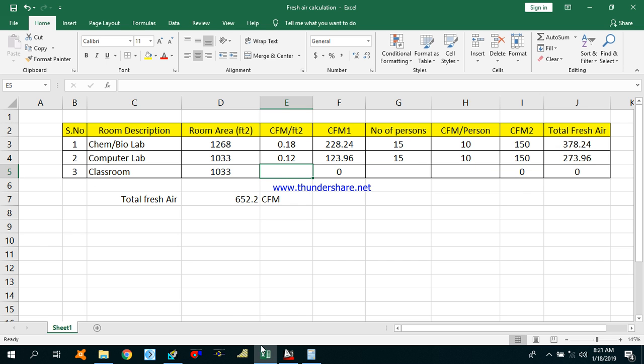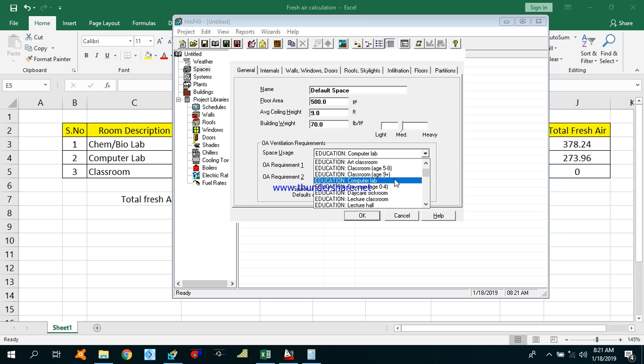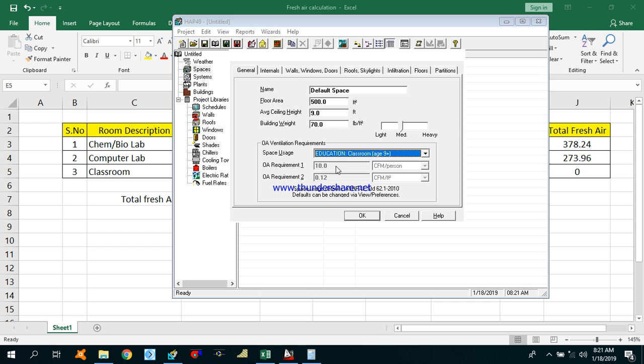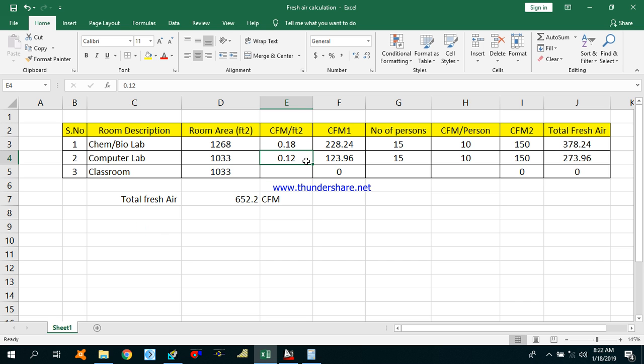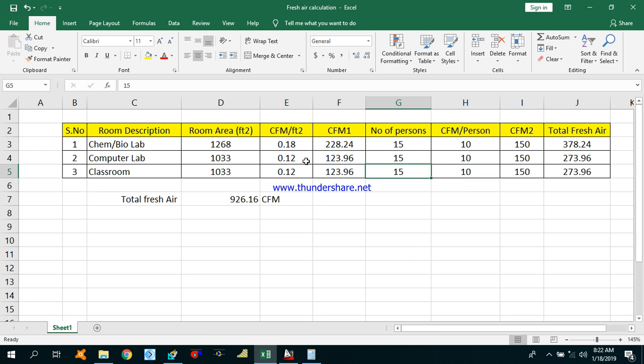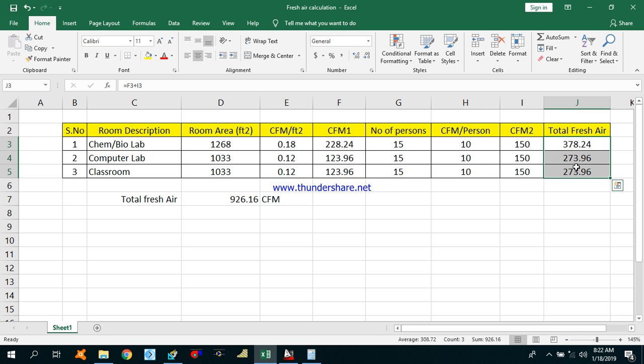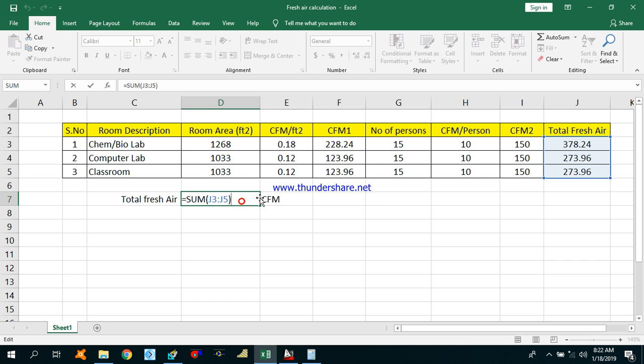For the classroom — education classroom for grade 6 students, age 9 plus — the CFM per person is 10 and CFM per square feet is 0.12, same as the computer lab. Using the same number of persons, the total CFM required for the classroom is again 274. The total fresh air CFM for all three areas — chemistry bio lab, computer lab, and classroom — is the sum of these three values.